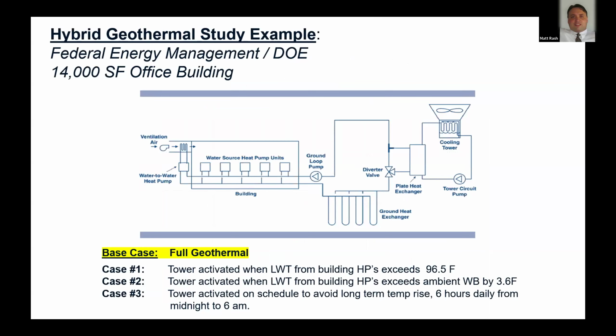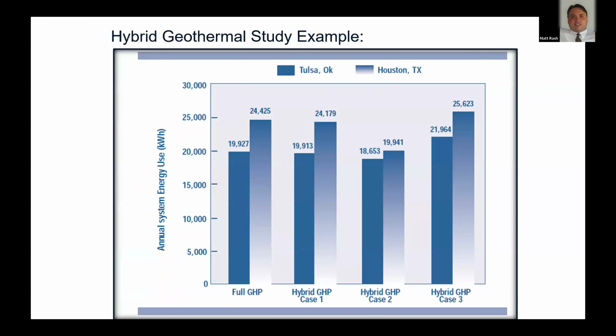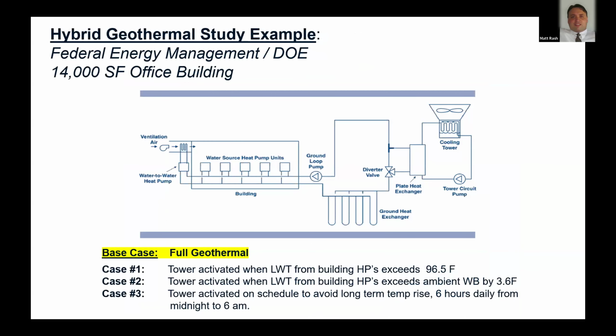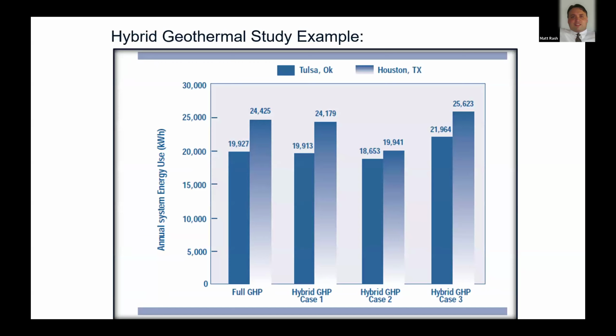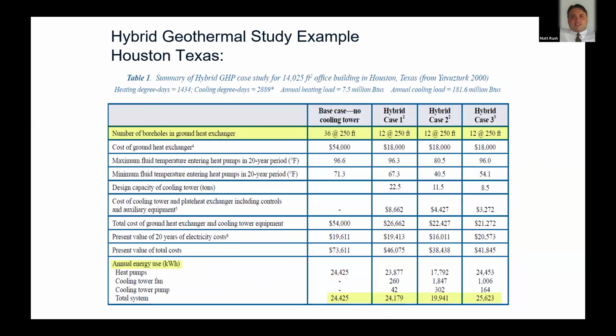To combat that, I think looking at hybrid VRF is very advantageous. There have been studies done with the DOE and other entities comparing full geothermal to hybrid systems, for a 14,000 square foot office building. They looked at this in Tulsa and Houston, Texas, and for very minimal impact, if not in some cases depending on how that backup tower was activated in the project, the hybrid case had a lower operating cost. Maybe slightly higher in one case, depending on how they operate the backup tower. They summarized this in terms of number of boreholes and total project cost, even with the towers.